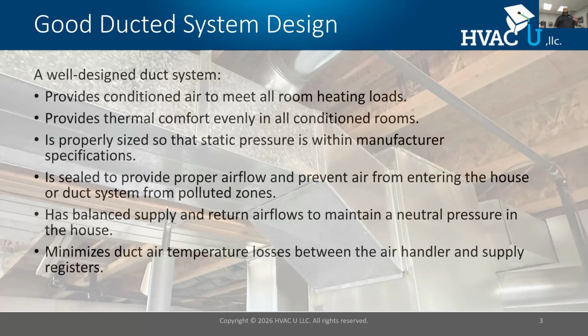A leaking duct system can cause some issues with the building pressures inside. We'll talk about that. And we want balanced supply and return. When we design a duct system, we design it so that if we're delivering a CFM to a room, we want the same CFM to return, except bathrooms and kitchens. So we'll discuss that. And we want insulation on our ducts if they're in unconditioned spaces. All right, so these are all common things that we run into with duct systems.